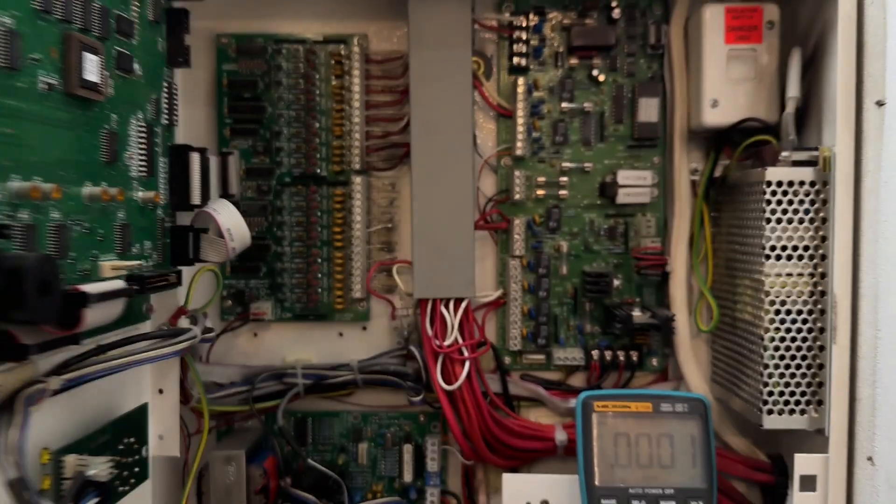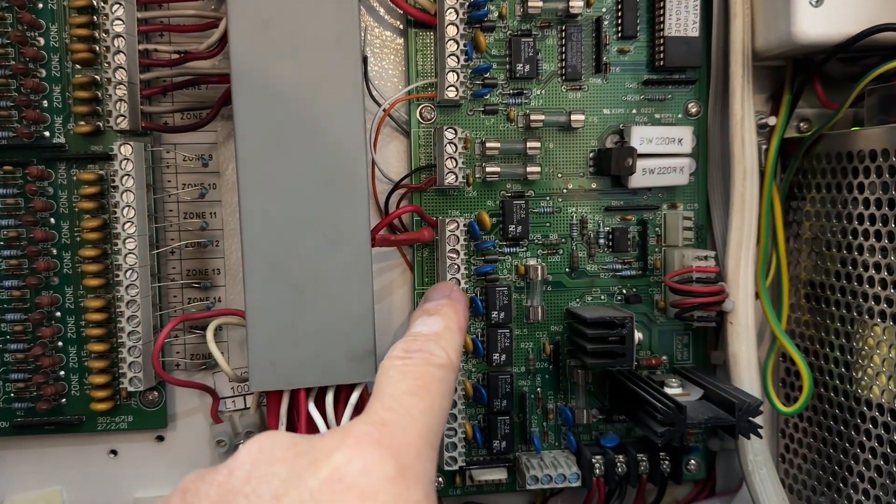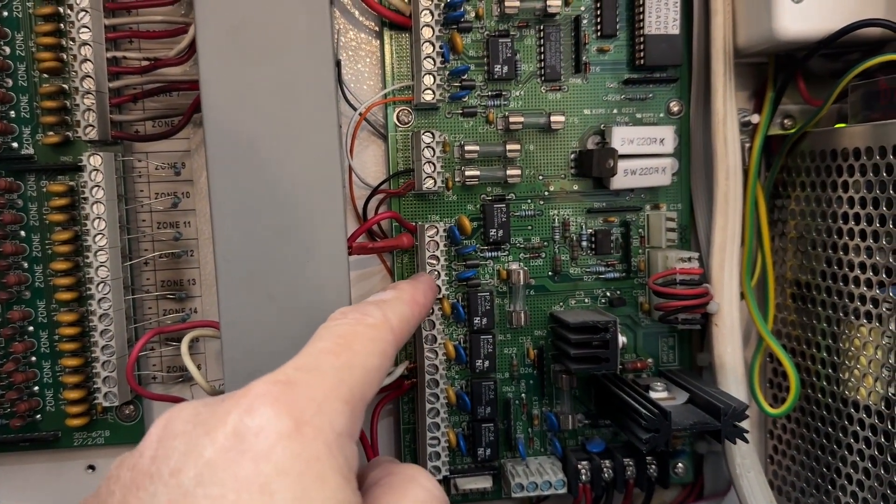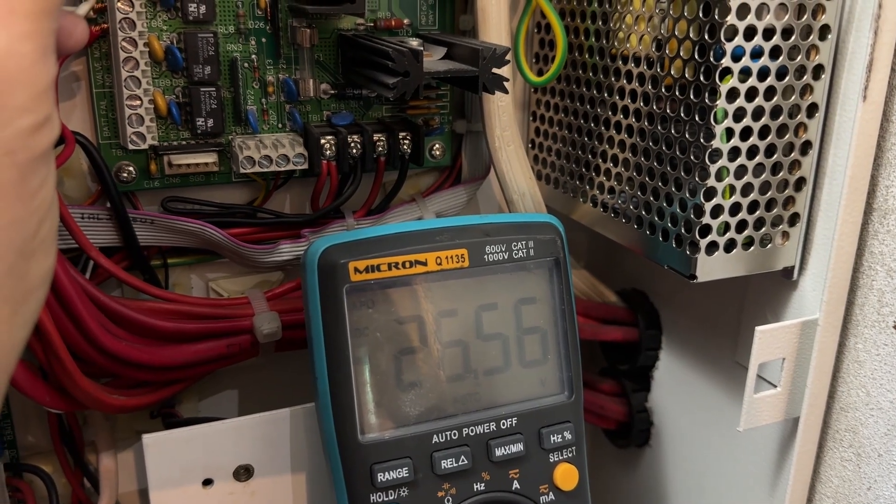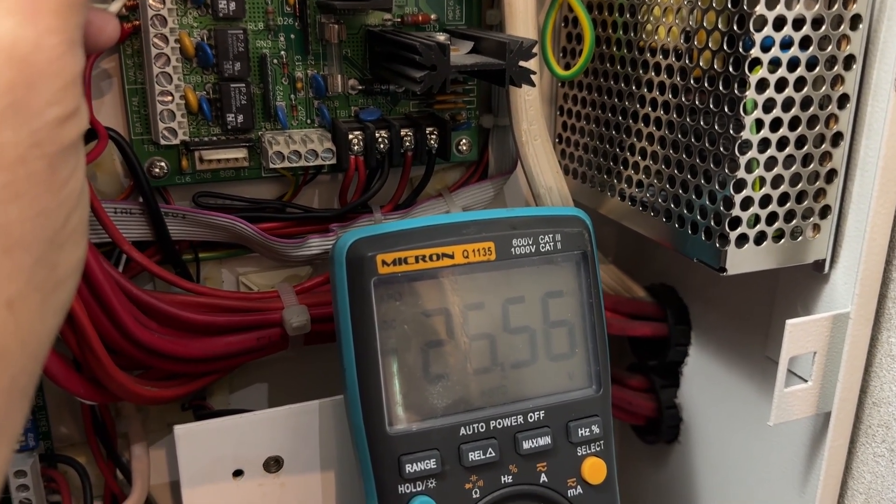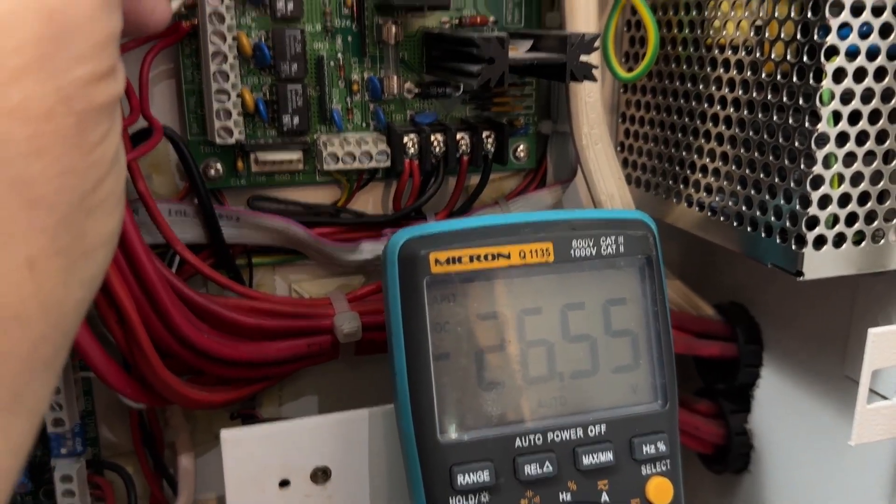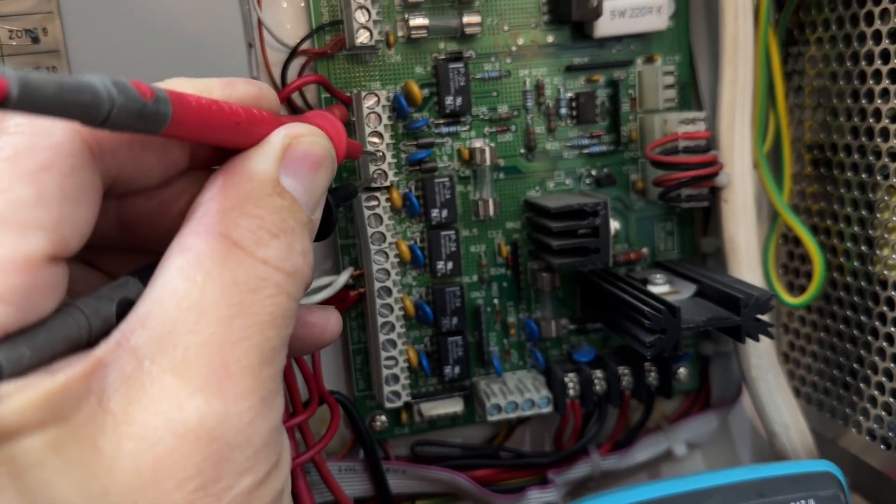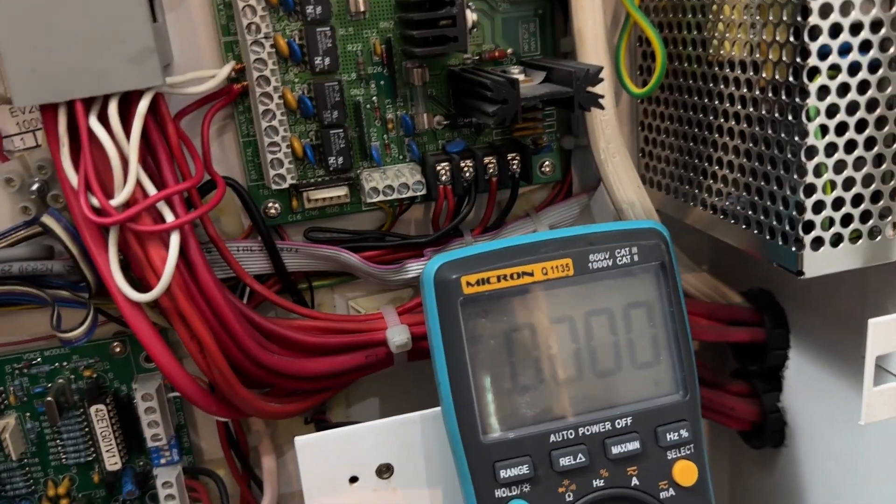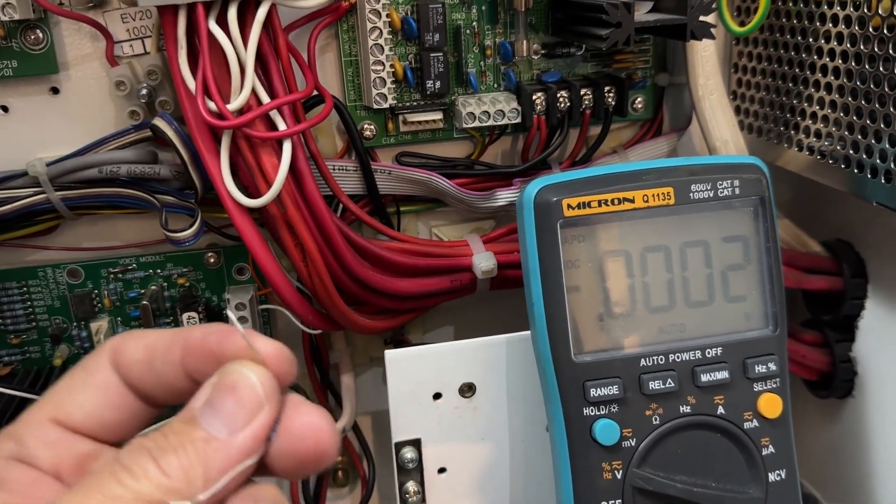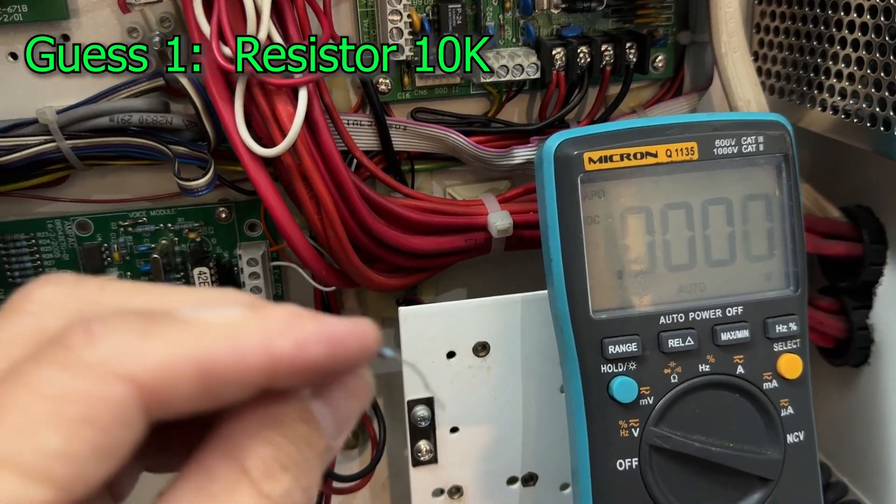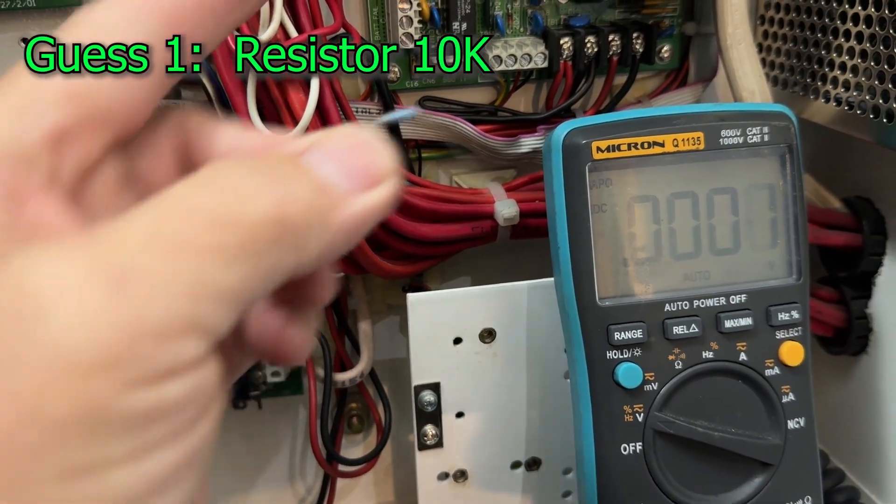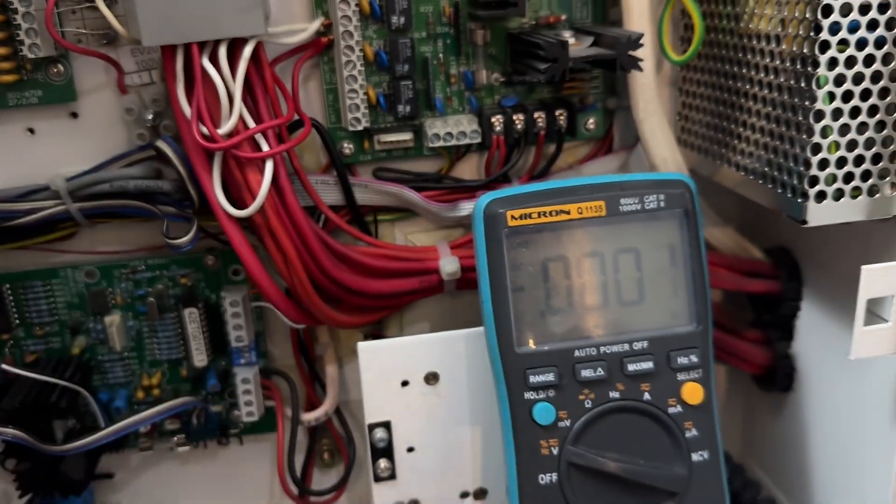Now let's check the voltage existing in this relay output. I got 25.5 voltage DC steady voltage from the fault relay. Okay, so we might have, my assumption, we might have a problem with the resistor. Okay, so I'm going to look for the resistor and try to replace that. This resistor and install a new one.